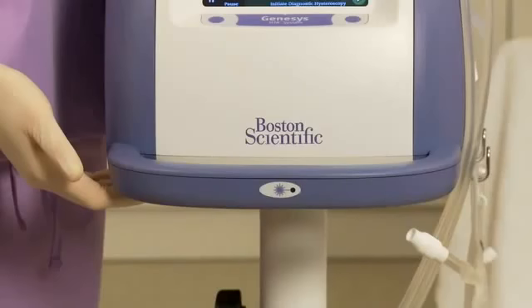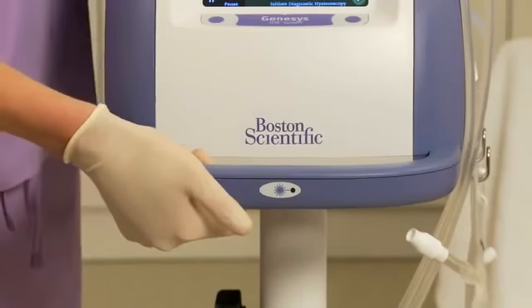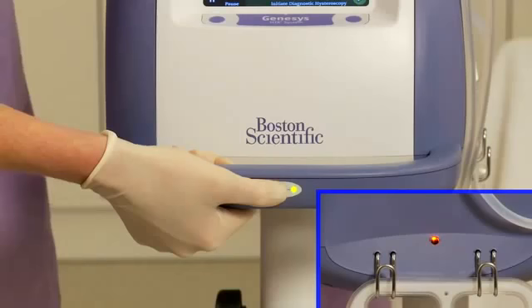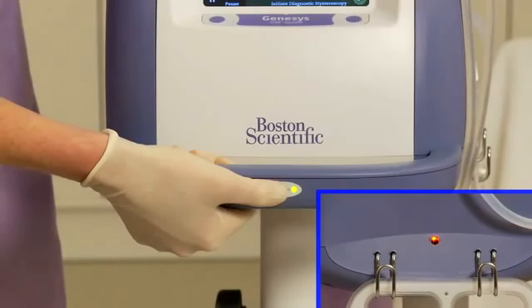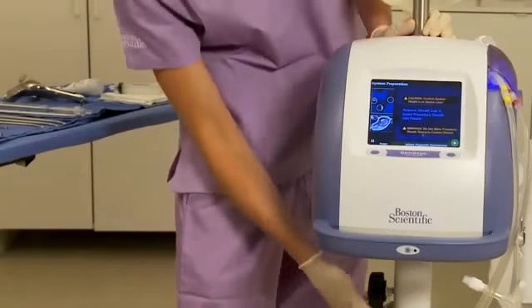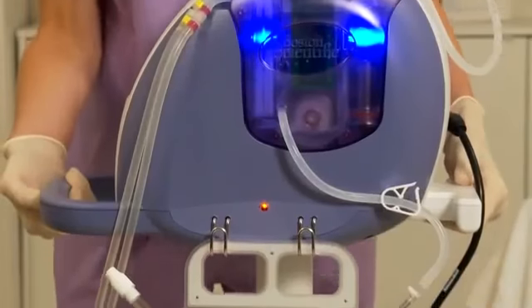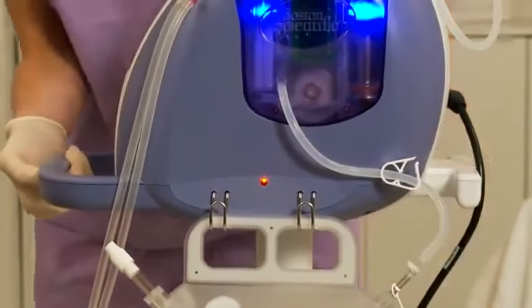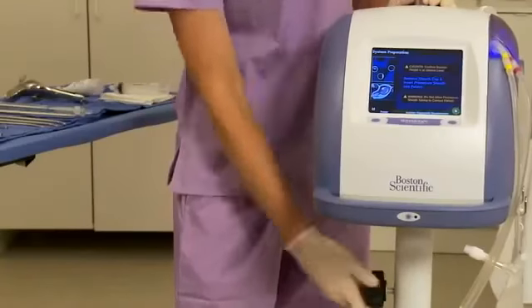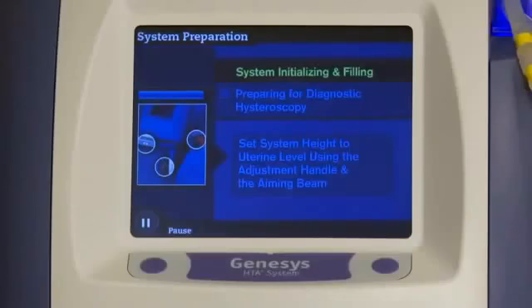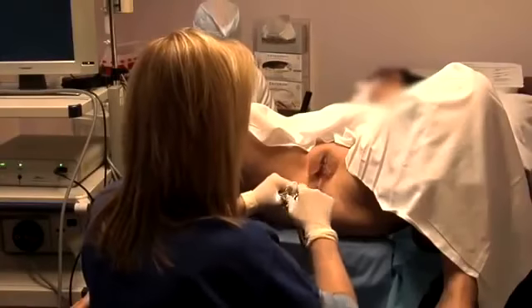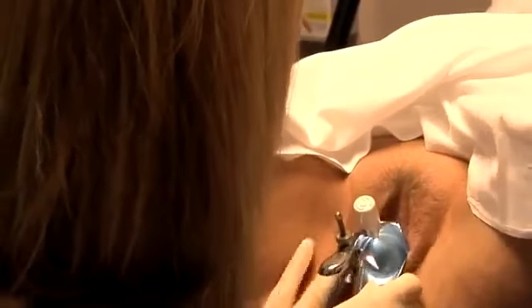Set the console height by aligning the console's handle or the laser aiming beam with the height of the patient's uterus. To adjust the height, simply loosen the adjustment knob and gently raise or lower the console to the proper height, and then retighten the knob. Setup is now complete. To prepare the patient, begin by exposing the cervix with a vaginal speculum. Ensure that the vaginal speculum has adequate length and width to provide a 360-degree view of the cervix.